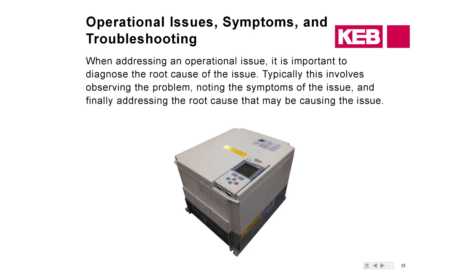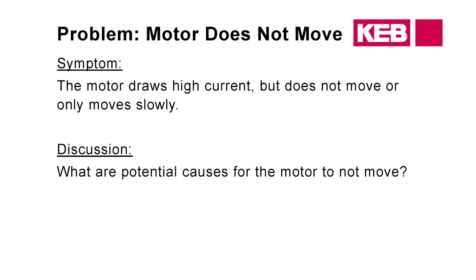The first symptom: motor doesn't move, motor's drawing high current. Troubleshooting — what do you guys usually do in the field? Check the brake first. Make sure the brake is picking. If your brake is not picking, obviously you're not going to move, and any changes that you make in the drive aren't going to have any impact if the brake is not picking.